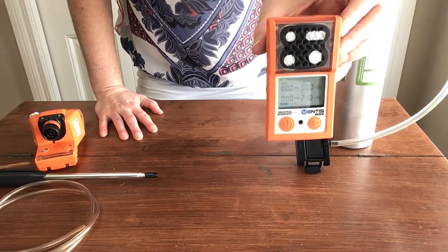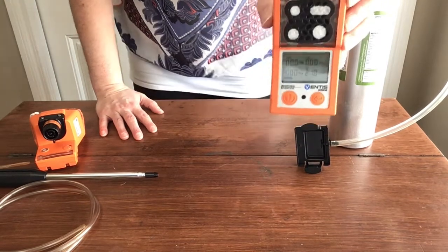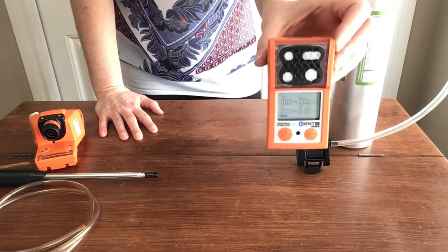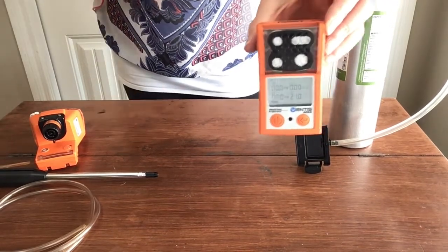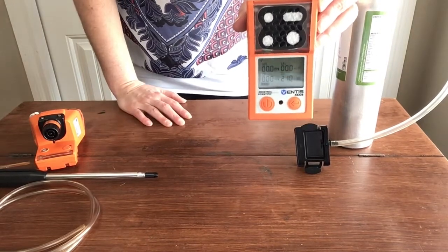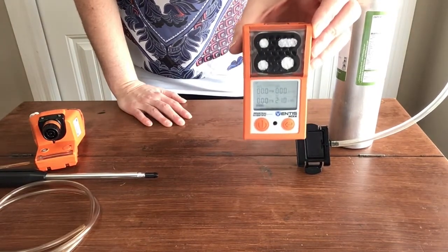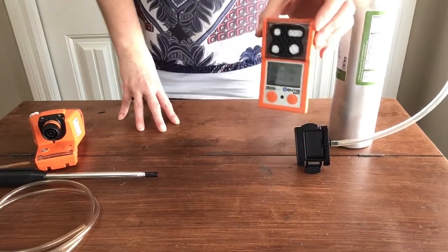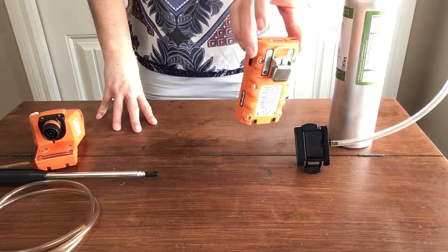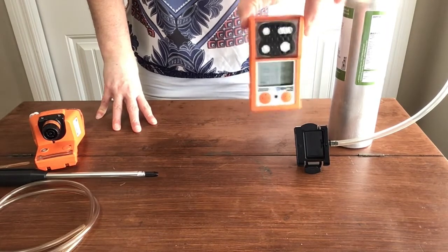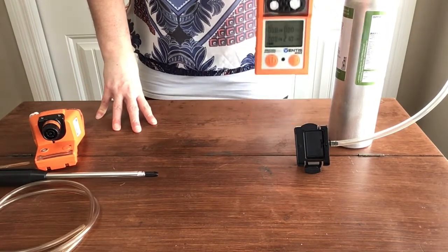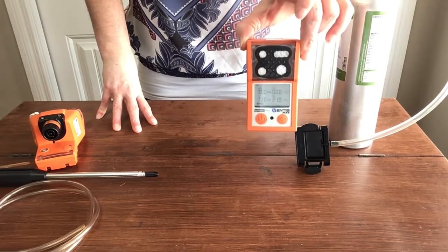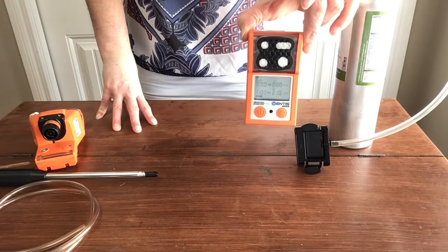The breathing zone, when we're talking about that, usually they'll clip it on a lapel or something like that. You just want to make sure that it's somewhere up near the mouth or the breathing area. So I think that's it for the unit itself. Now, when you're using this to go into a confined space as a piece of PPE, you'll use it just like this, okay? You can, however, use this to actually monitor a confined space to make sure it's safe before any workers go into the space.